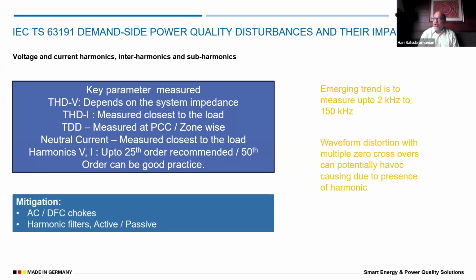Harmonics mitigation requires a lot of design knowledge, with which we should be able to do it either with DC or AC chokes. I have a spelling mistake here. And then the harmonic filters, which can be active or passive. There is an emerging trend to monitor 2 kilohertz to 150 kilohertz also, but it is still in the books. We should watch how this emerges, because a lot of sensitive manufacturers have started supplying devices or equipment in the system which control the lower order harmonics but give the higher order harmonics very badly. So that is still a problem. When new equipment comes in, we also have to be clearly aware of the harmonic frequencies beyond 2 kilohertz.